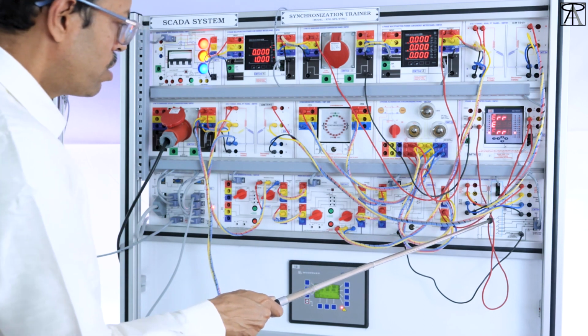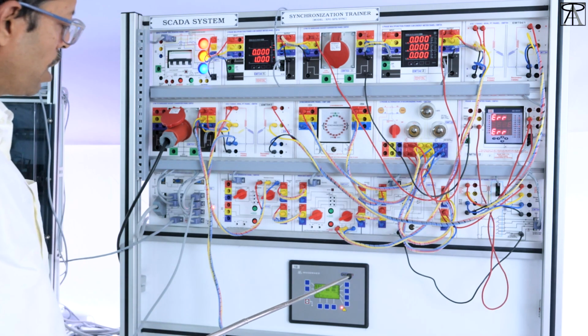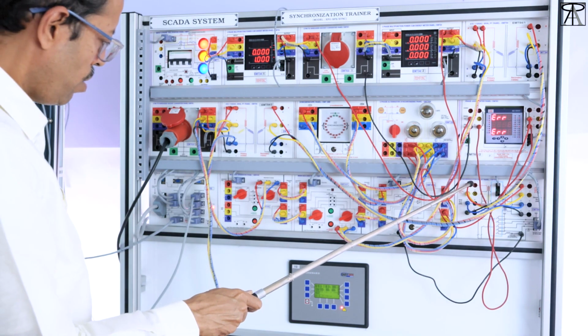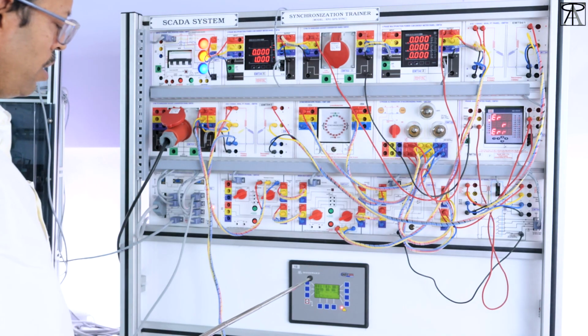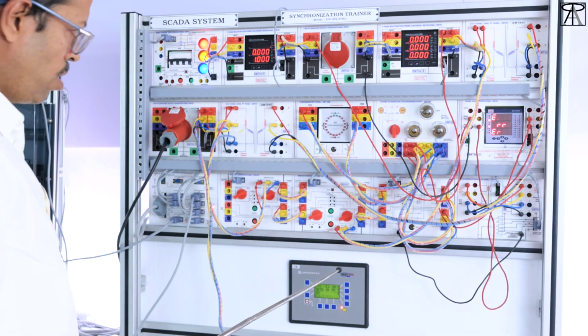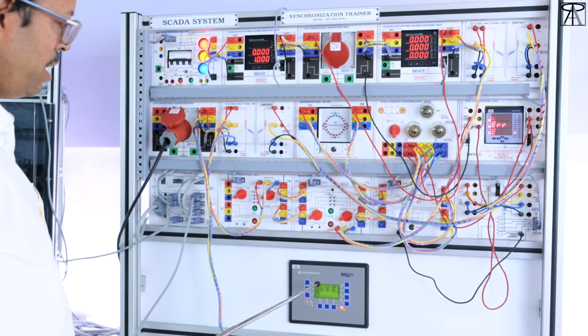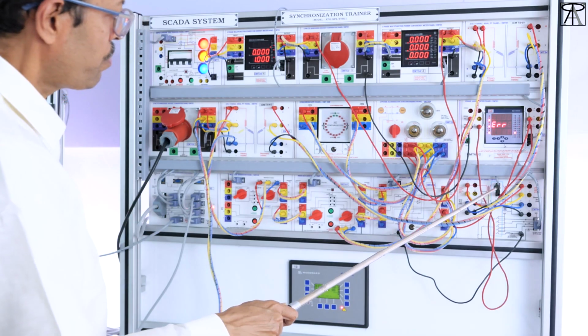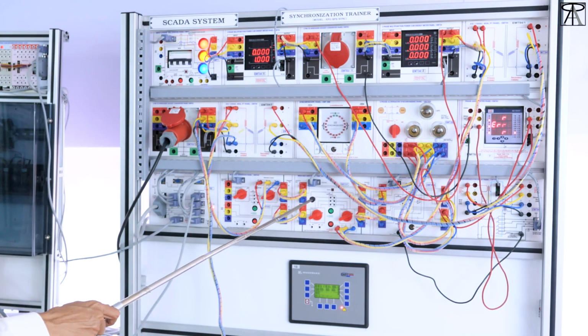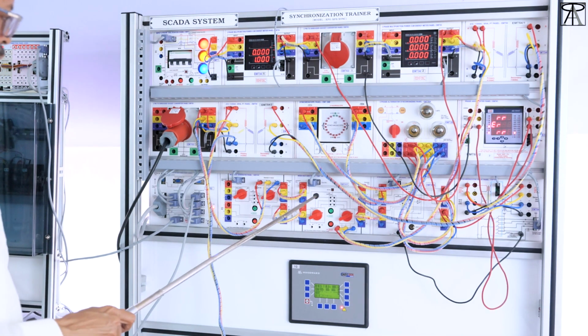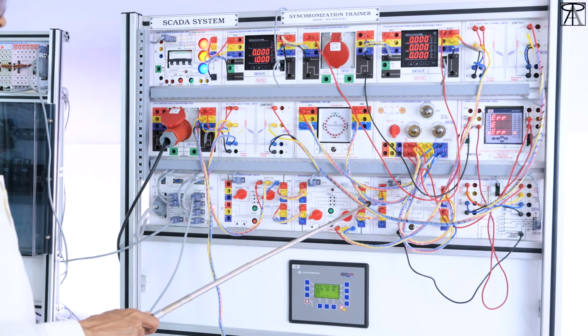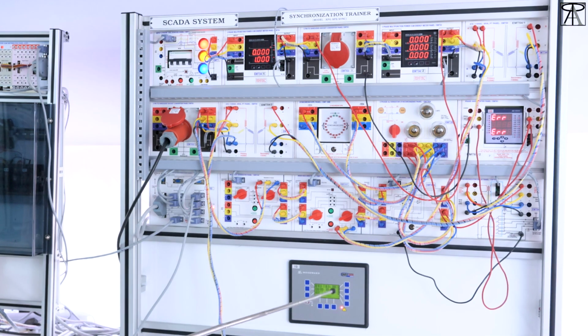This is for the synchronization relay purpose. We have used an automatic and manual synchronization relay. The parameters needed we have brought back to this panel. And this is for the automatic and manual switches for the synchroscope. This synchronization relay can perform the experiment in automatic and manual synchronization, and directly from the generation output and grid power supply, it synchronizes automatically once the setting is done.